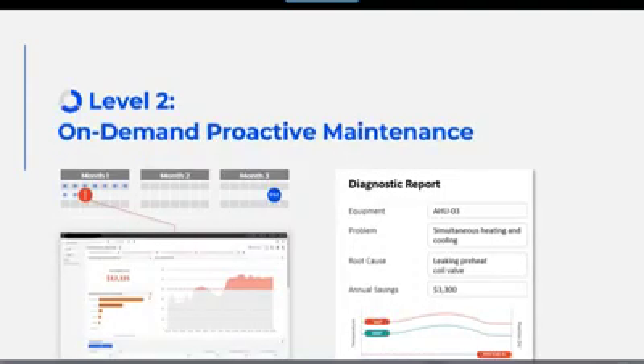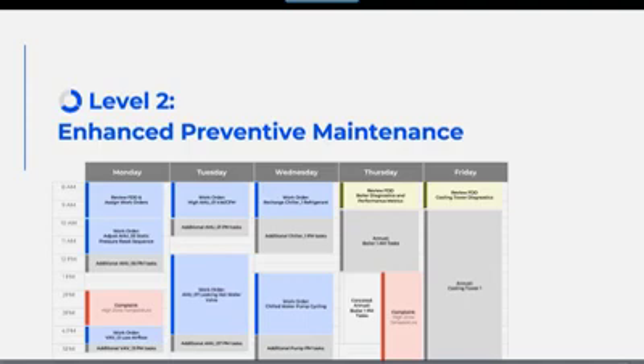A second approach with critical equipment is more on-demand maintenance. Again with critical pieces of equipment, we can use FDD tools to address issues as they come up. Instead of my tech looking at the FDD tool only before a normal site visit, they can check it in between, from a network operations center. When an issue flags at a certain severity or dollar amount, a truck can roll to that site to take care of it. Once the issue is resolved, they run through the normal scheduled PM checks. So it's a more intense usage of an FDD tool on critical equipment.